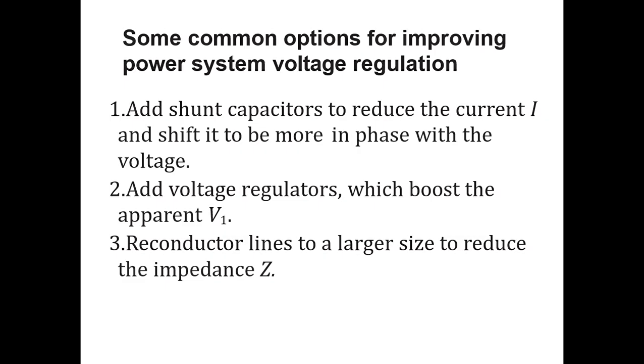Second thing, add voltage regulators which boost the apparent voltage. So we have to add the voltage regulators, either OLTCs, that is on load tap changers, or off load tap changers. If you add these OLTCs, OFTCs or some different kinds of voltage regulators, then definitely we are going to improve the voltage regulation of the power system. Then the third thing that we are going to discuss here is to reconductor lines to a larger size to reduce the impedance. This is the third method that we can use to improve the voltage regulation of the power system.